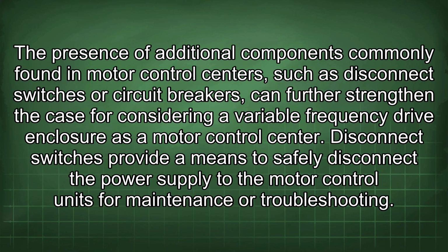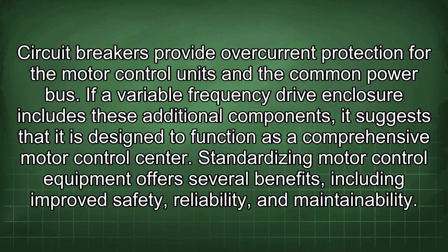The presence of additional components commonly found in motor control centers, such as disconnect switches or circuit breakers, can further strengthen the case for considering a variable frequency drive enclosure as a motor control center. Disconnect switches provide a means to safely disconnect the power supply to the motor control units for maintenance or troubleshooting. Circuit breakers provide overcurrent protection for the motor control units and the common power bus. If a variable frequency drive enclosure includes these additional components, it suggests that it is designed to function as a comprehensive motor control center. Standardizing motor control equipment offers several benefits, including improved safety, reliability, and maintainability.